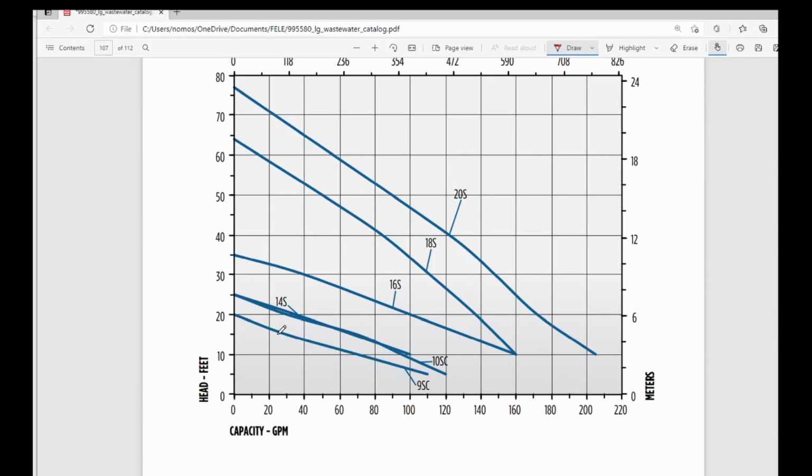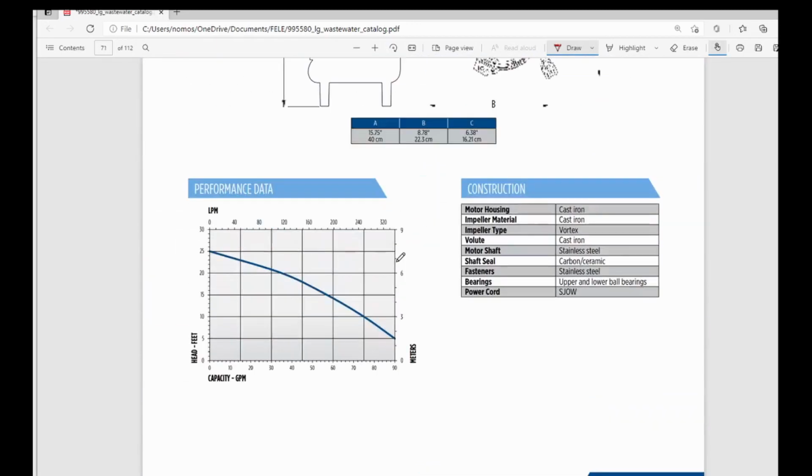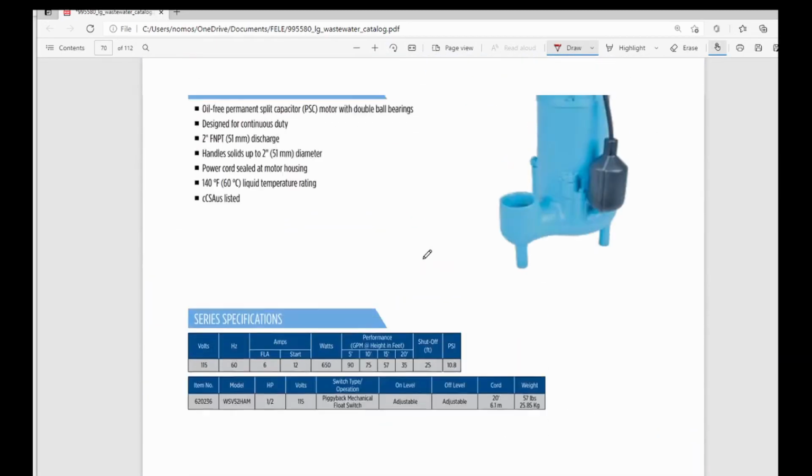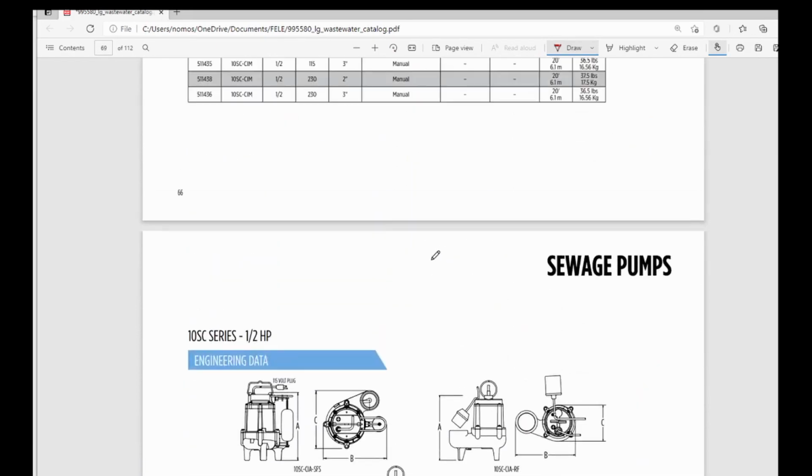And my 14S and my 10S, let me write that. 21 gallons a minute at 17 feet. We're probably right here. That looks about right. So it is within the curve of the 14S and the 10. 14S, there's the 14S. See, look at all these other pumps. Weren't even included on the chart.